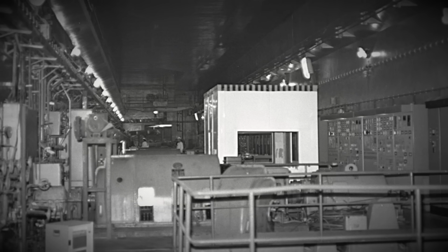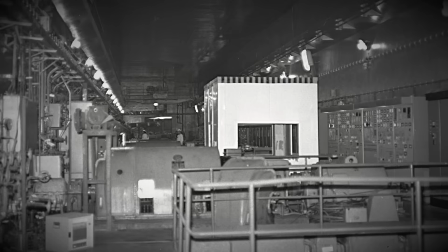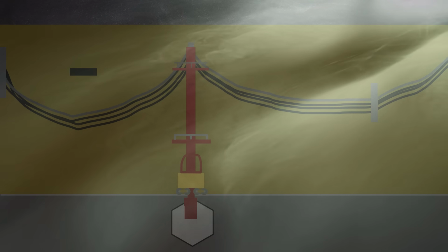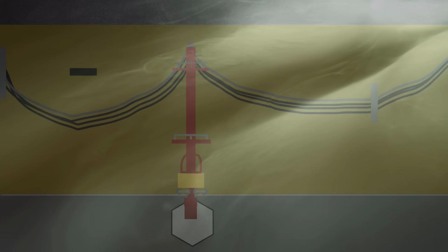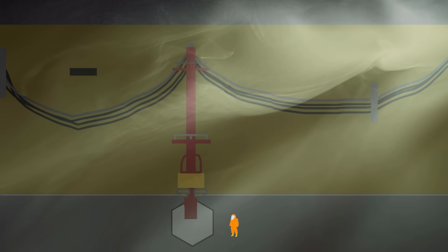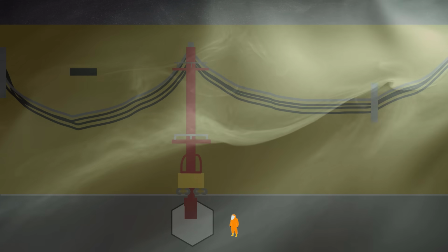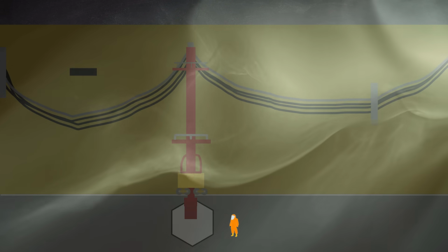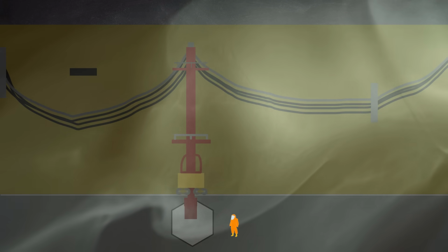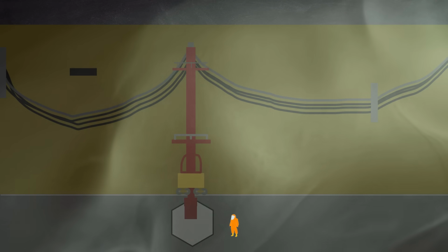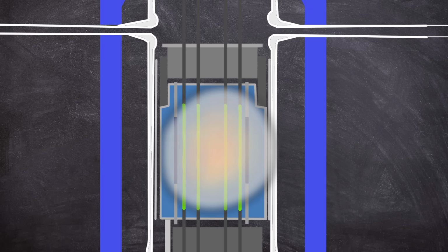If the technical channel couldn't be closed within half an hour of the initial leak, potentially all of the gas could have escaped from the core, leaving no chance for the reactor to cool down. After entering the hall in protective gear, an operator managed to move the smashed up fuel rod and was able to manually seal off channel H04, with the help of the refueling machine, sealing off the leak. At 1:04 p.m., the compressor finally succeeded in reaching the required speed to cool the core.